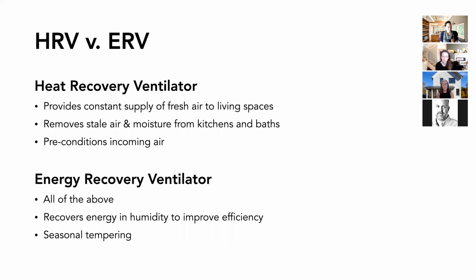Next slide, Parlin. Thanks. You've probably heard that there are heat recovery ventilators as well as energy recovery ventilators. They both supply fresh air and extract stale air. The heat recovery ventilator has a core that's made of a ceramic material. In the wintertime, when we are warming up our air on the inside of the home, the extracted air, the air that's leaving the bathrooms and the kitchens, is warm air. That heats up the core on the way out. And then likewise, the incoming air passes across that core and gets tempered on its way into our homes. So it has that preconditioning element to the heat recovery ventilator.